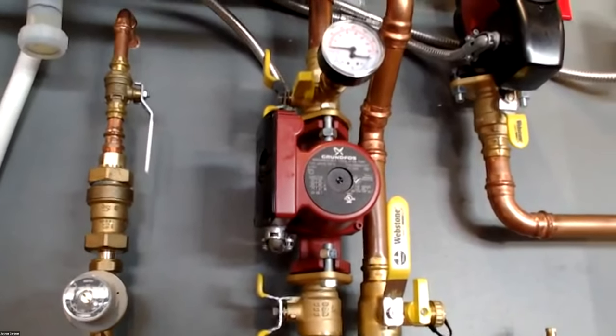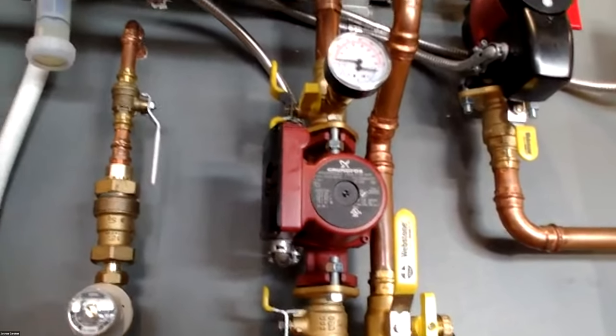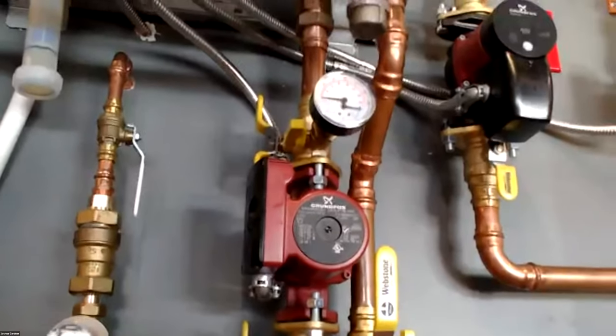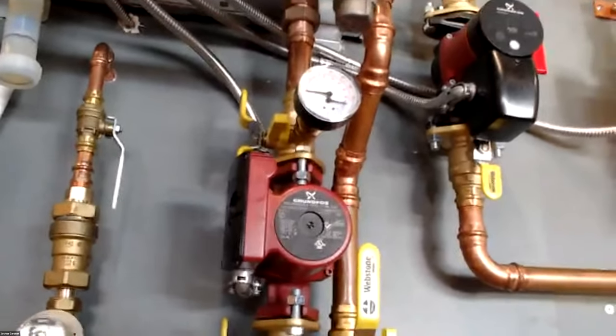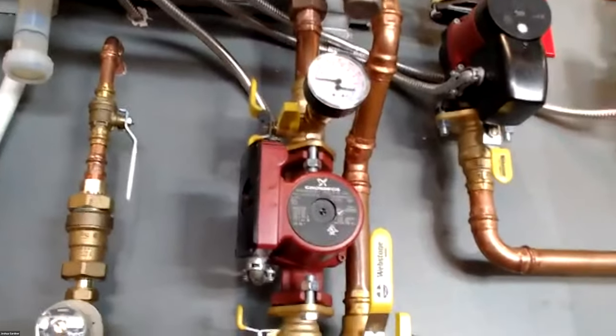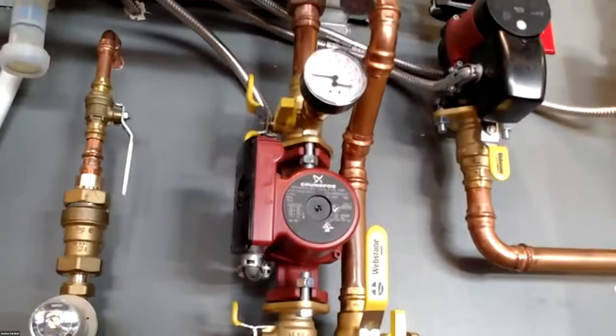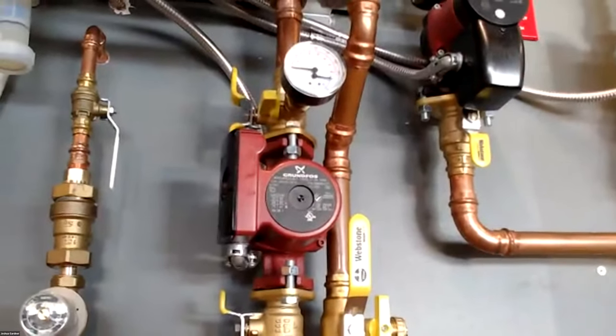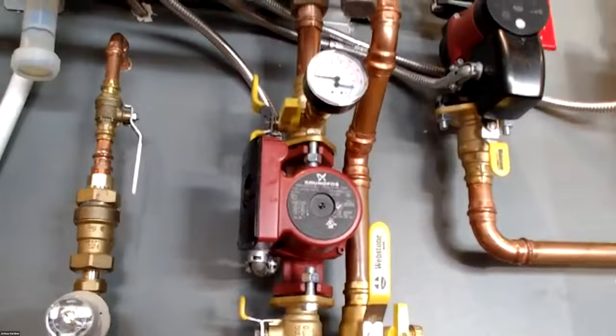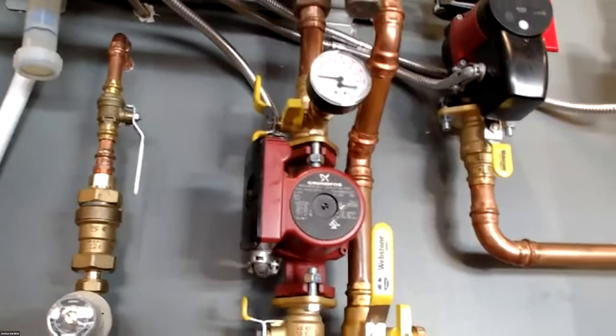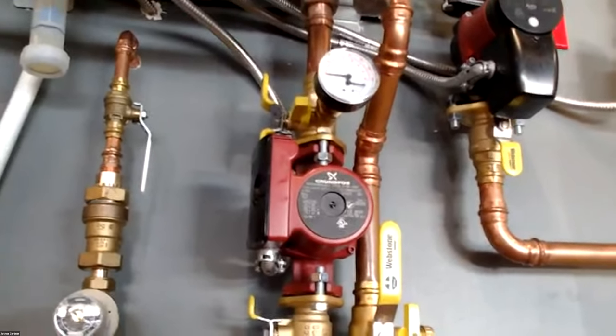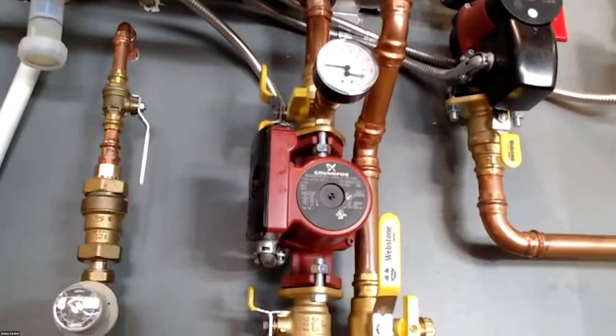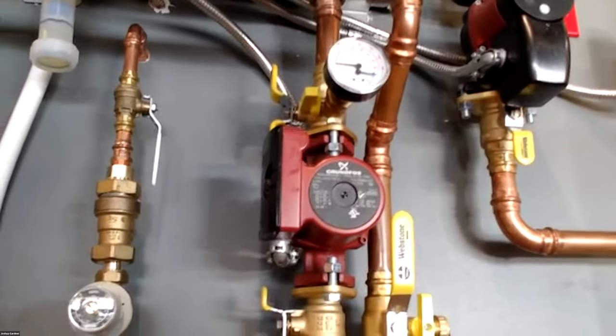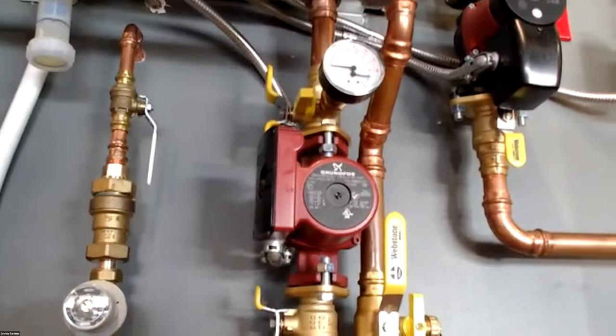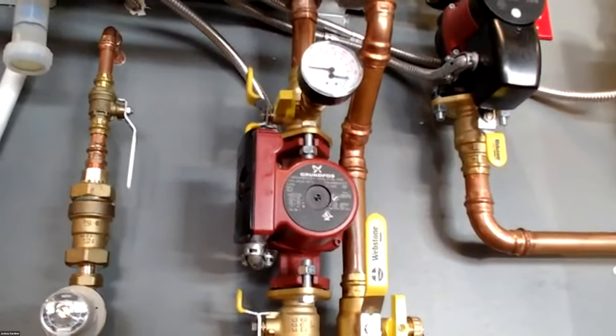Those pumps have a feature where they actually shut off. So we'll have delta T and we'll have high temp lockout. Stay away from those. Great pumps on the secondary side, not great boiler pumps. So on the 110 and the 155, you can use a 0015 ECM Taco, but it's going to be on speed 3 high. The low and medium speeds have that safety feature. The high speed doesn't. So you're totally fine going with that.